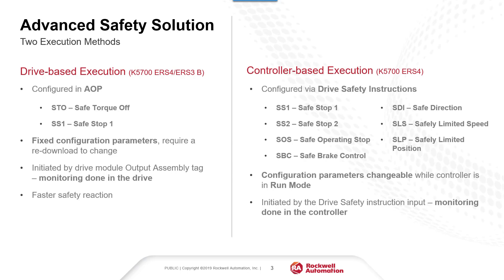The other execution method is controller-based. The parameters for the safety function are now configured in the drive safety instruction in the safety task program. The available safety functions are Safe Stop 1, Safe Stop 2, Safe Operating Stop, Safe Brake Control, Safe Direction, Safely Limited Speed, and Safely Limited Position.